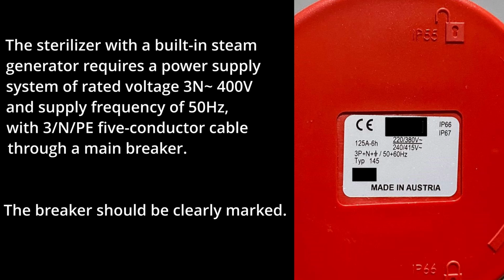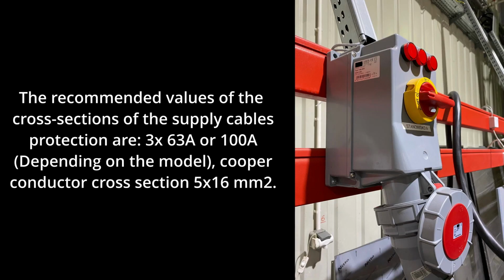The sterilizer with a built-in steam generator requires a power supply system of 3-phase 400 volts and supply frequency of 50 Hz with 3-phase, neutral, protective earth, 5-conductor cable through a main breaker. The recommended values of the cross-sections of the supply cable's protection are 3 by 63 amperes or 100 amperes depending on the model, and copper conductor cross-section 5 by 16 square millimeters.